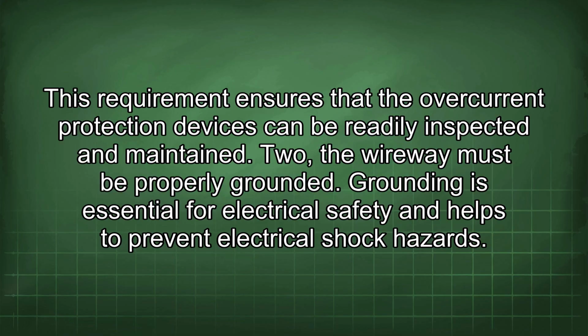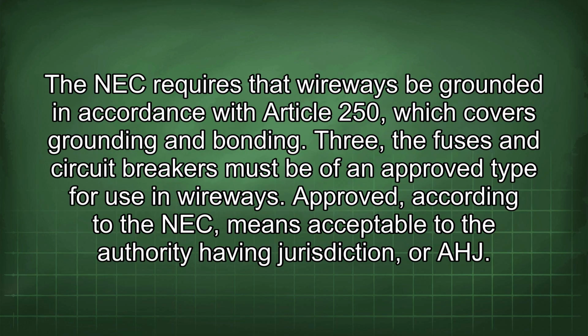2. The wireway must be properly grounded. Grounding is essential for electrical safety and helps to prevent electrical shock hazards. The NEC requires that wireways be grounded in accordance with Article 250, which covers grounding and bonding.